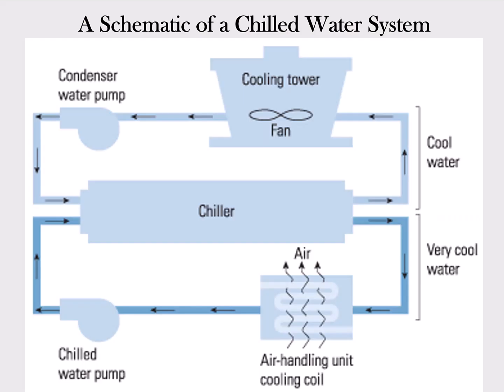So if you go back to this gray picture, we've got a refrigerant that's running, cooling off water. This treated water is kind of like water in a radiator system for your car, except we're trying to make it colder. You might have 50-something degree water that you're pumping around and pushing through air handlers, with a pump that keeps the cycle going around and around, continually cooling off the water.